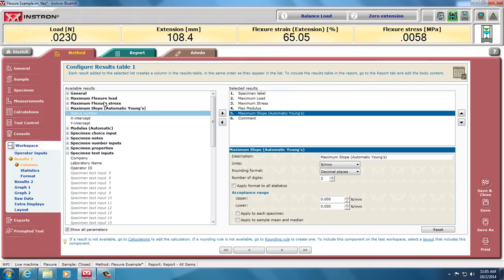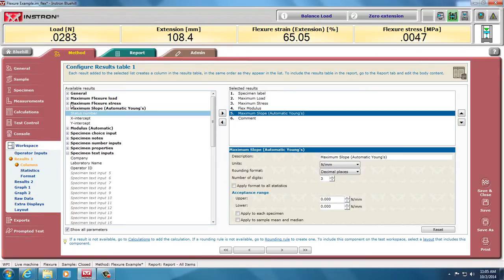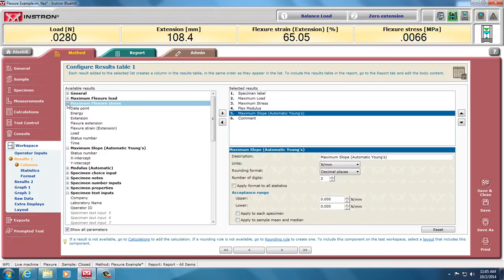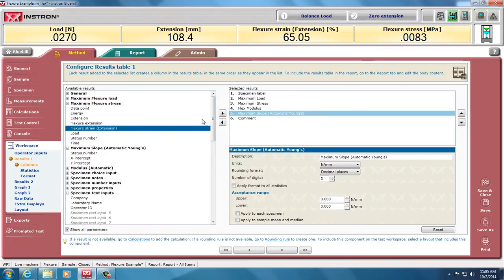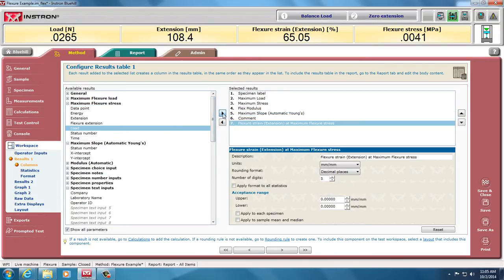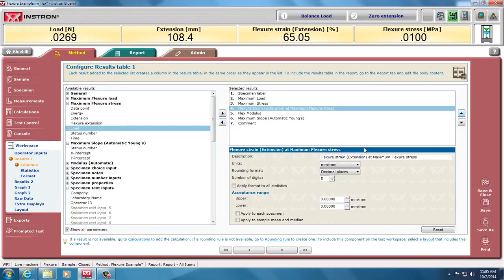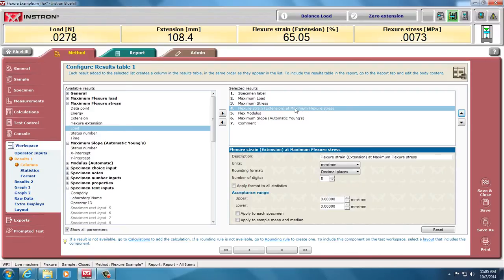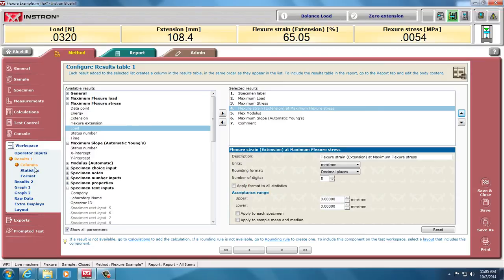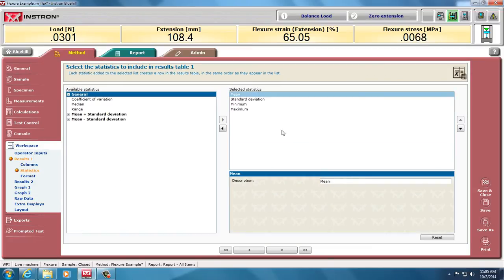There are many other different types of calculations you can make, including stress. You can also measure strain. So I could actually measure at the maximum flexural stress, what is the flexural strain? I could put that up next to my maximum stress. So it's flexural strain at maximum flexural stress. You could also calculate at max strain what are the stress and strain, but I would have to do that under calculations. I have to select that as one of the type of calculations we can do. It'll do statistics at the bottom if we'd like it to do those.